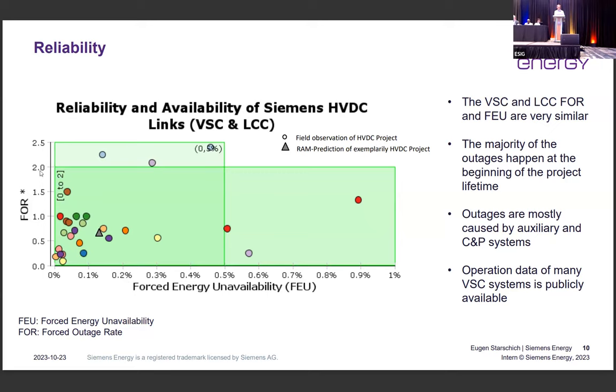What we see right now is a forced outage rate of 2. That means a converter fails up to 2 times a year. And looking over a year, 0.5% of the time the converter is not available due to the forced energy unavailability, so unscheduled failure or unscheduled unavailability.